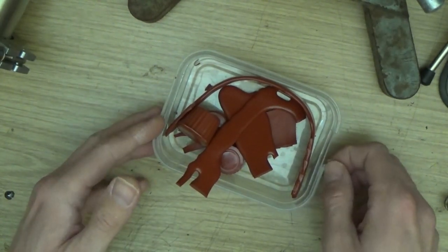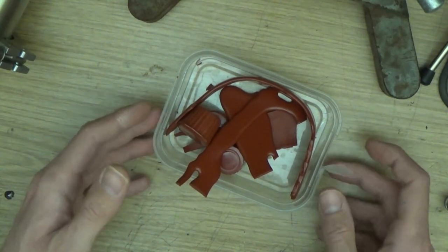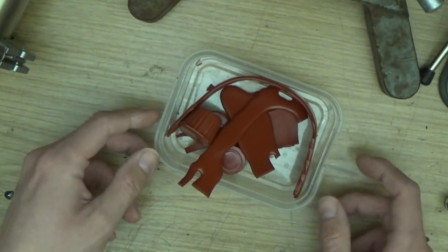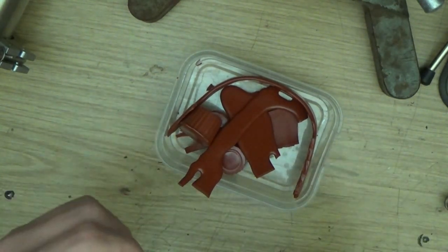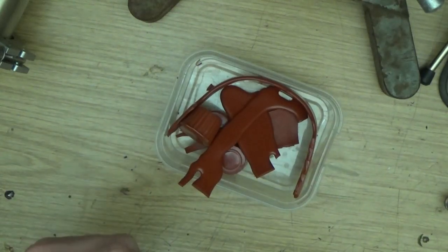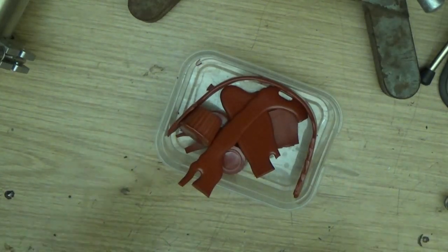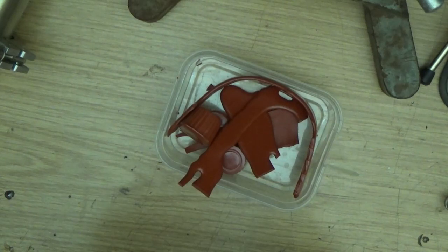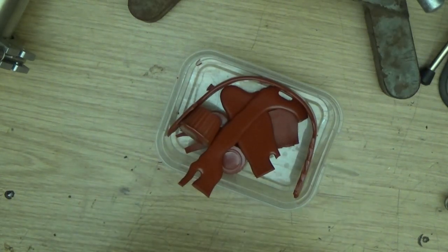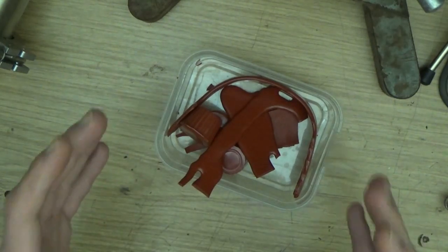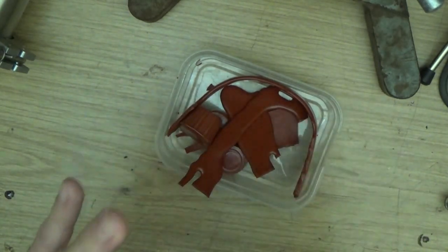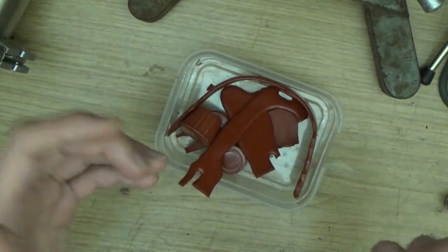There are commercial products for vacuum sealing. The most professional one is called Torr Seal, and I think it's by Varian or Agilent. Torr Seal is a vacuum epoxy that can be machined, and it's pretty good, but it's also very, very expensive. The slightly worse, but still very good alternative is called Hysol 1C, and it is completely impossible to find in Europe.